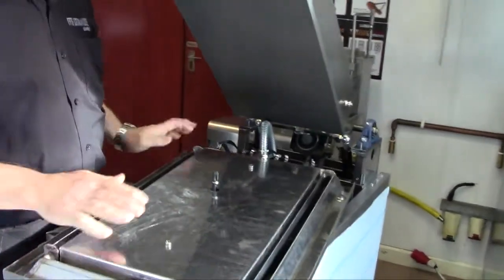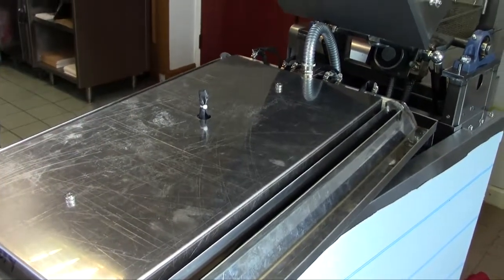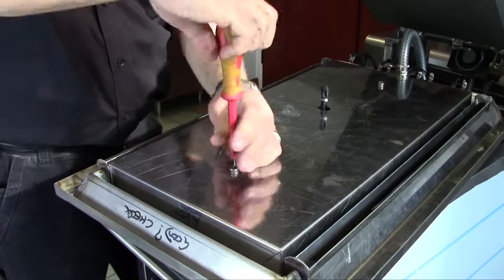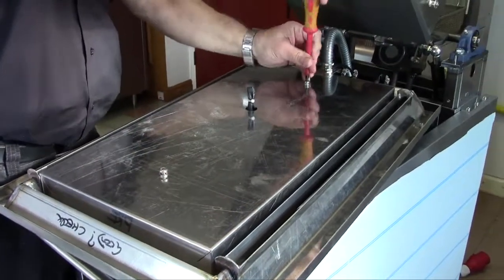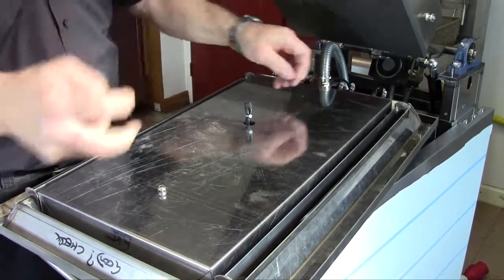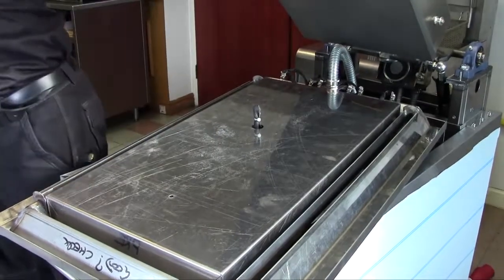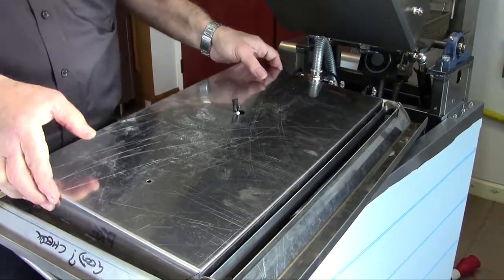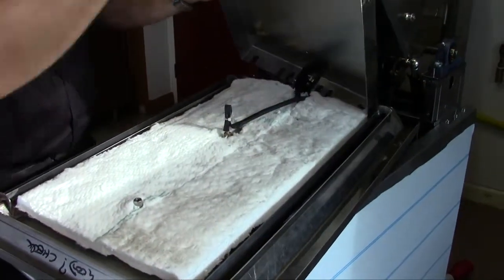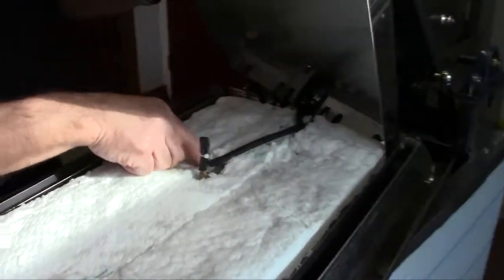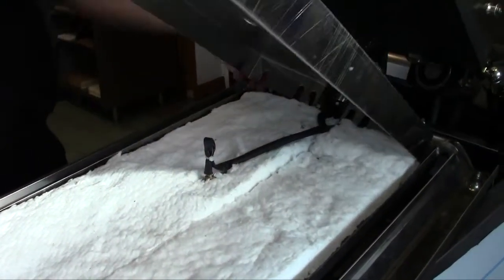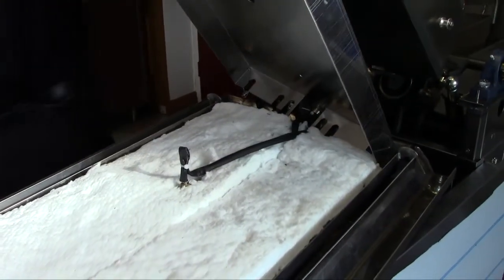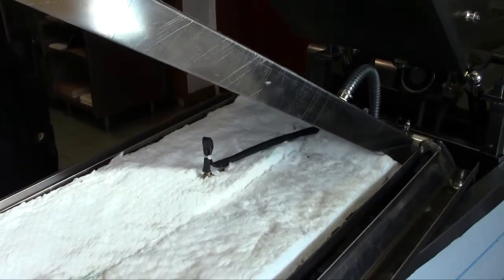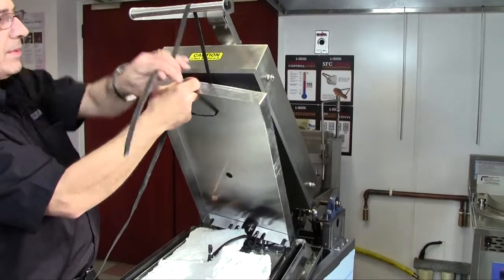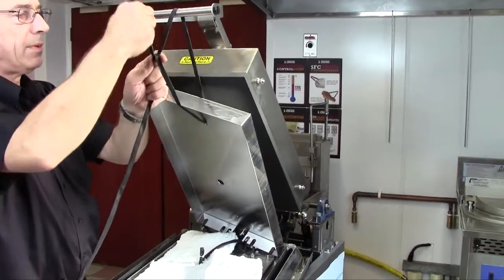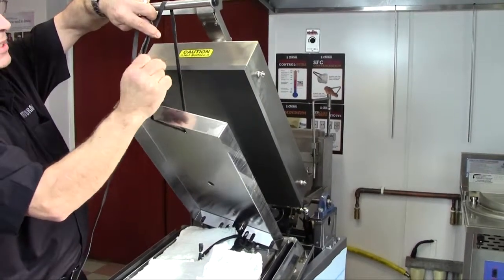Now what you need to do is turn the plate over at an angle, so it's resting on top, upside down. Then you remove the 2 screws holding the plate. See, this is your probe, and the high limit is fed underneath this. What I find easy to do is just basically tie it up out of the way. Use wire or whatever you've got handy, just to keep it out of harm's way.